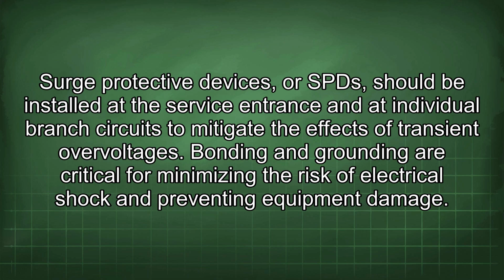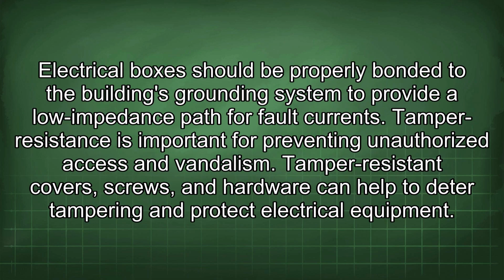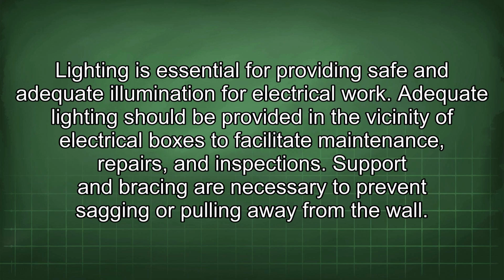effects of transient overvoltages. Bonding and grounding are critical for minimizing the risk of electrical shock and preventing equipment damage. Electrical boxes should be properly bonded to the building's grounding system to provide a low impedance path for fault currents. Tamper resistance is important for preventing unauthorized access and vandalism. Tamper-resistant covers, screws, and hardware can help to deter tampering and protect electrical equipment. Lighting is essential for providing safe and adequate illumination for electrical work. Adequate lighting should be provided in the vicinity of electrical boxes to facilitate maintenance, repairs, and inspections.